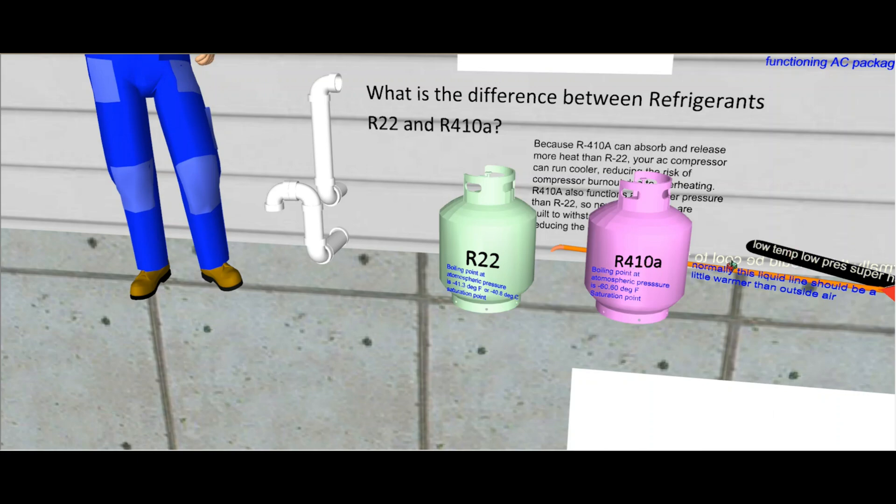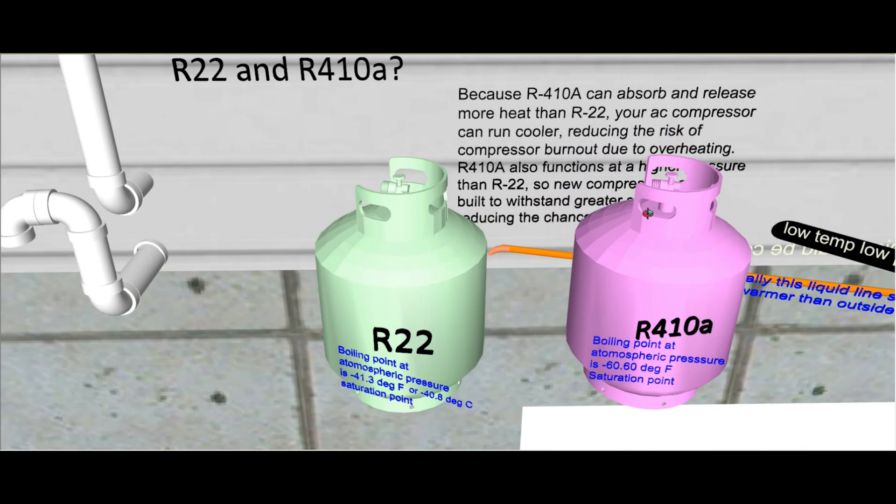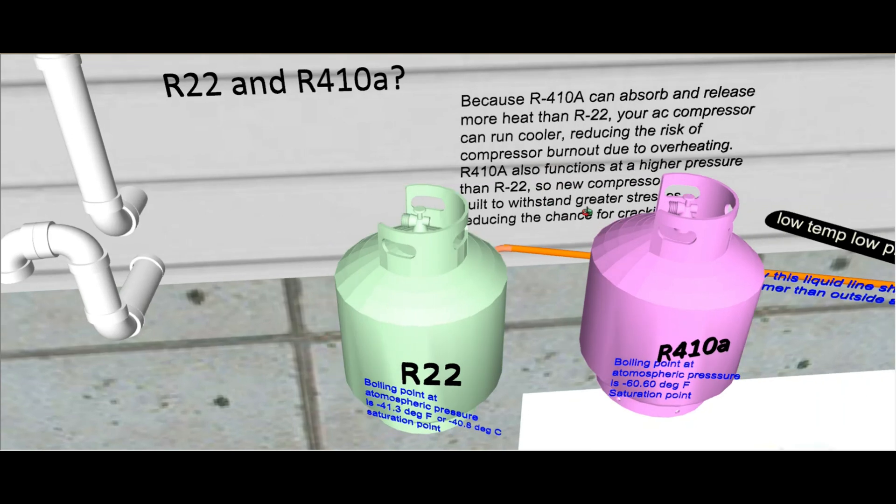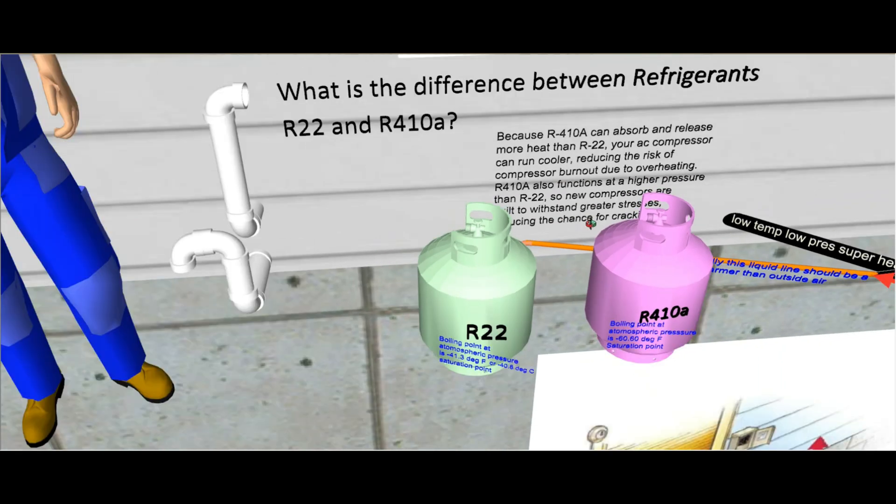What's the difference between them? Well, as you can see here, the 410A can absorb and release more heat than R-22, and your AC compressor which is found in the condenser can run cooler, reducing the risk of compressor burnout due to overheating. It also has a larger range of pressures on it, which helps because we want to manipulate the refrigerant that is located in these lines because we want it to absorb heat and reject heat and go in a circle and thereby cool down your house. So let's figure out how they did that.